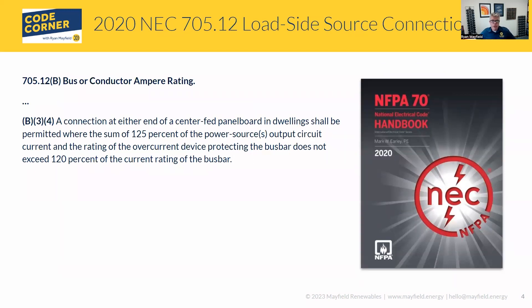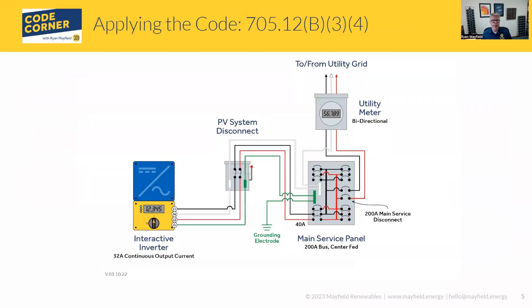The other section I wanted to talk about today is B34, and it talks about center-fed panel boards. So in dwellings — this is very specific to residential applications — we have a lot of existing panel boards, main service panels, where it's a center-fed panel. And if you go back and look at what we talked about with the 120% rule in B32, it talks about having the power production source — our PV system — where that interconnection has to be at the opposite end of the utility source when we're utilizing that 120% rule. This allowance is saying that we can still utilize that 120% rule even if you have a center-fed panel board.